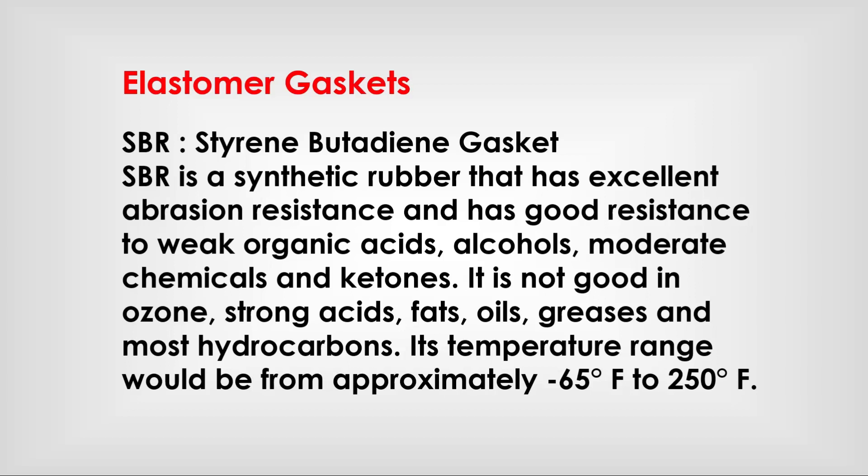Elastomer gasket — SBR (Styrene Butadiene Rubber): SBR is a synthetic rubber that has excellent abrasion resistance and good resistance to weak organic acids, alcohols, moderate chemicals, and ketones. It is not good against ozone, strong acids, fats, oils, greases, and most hydrocarbons. Its temperature range is approximately -65°F to 250°F.